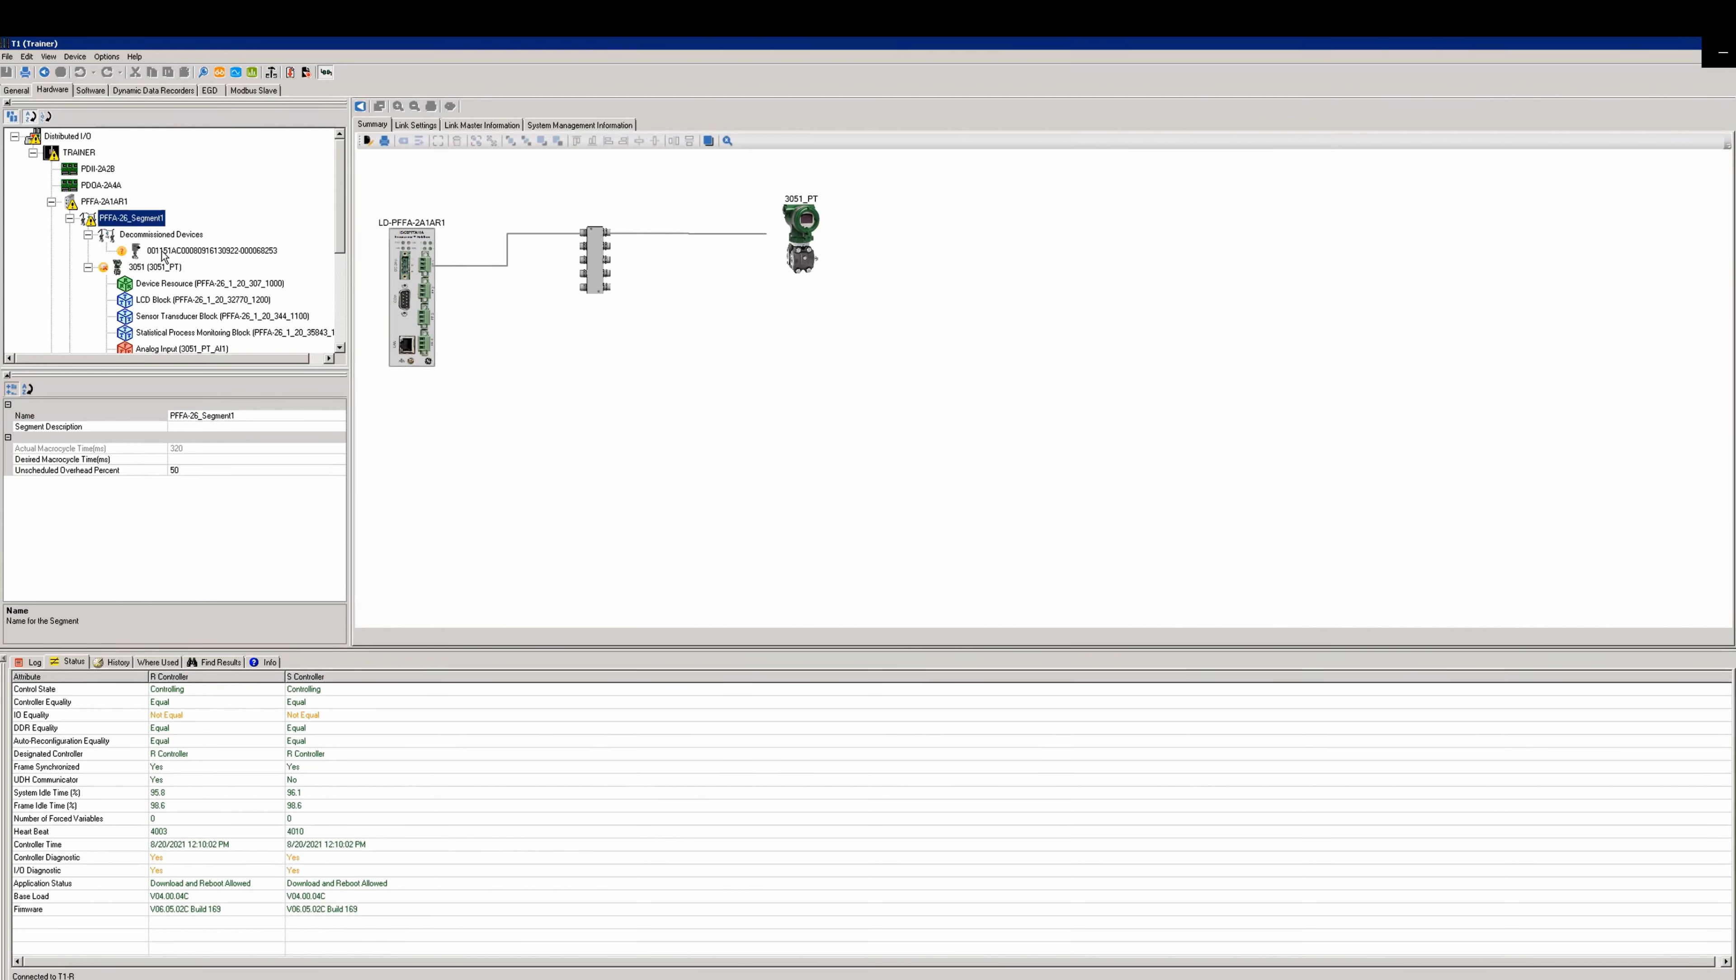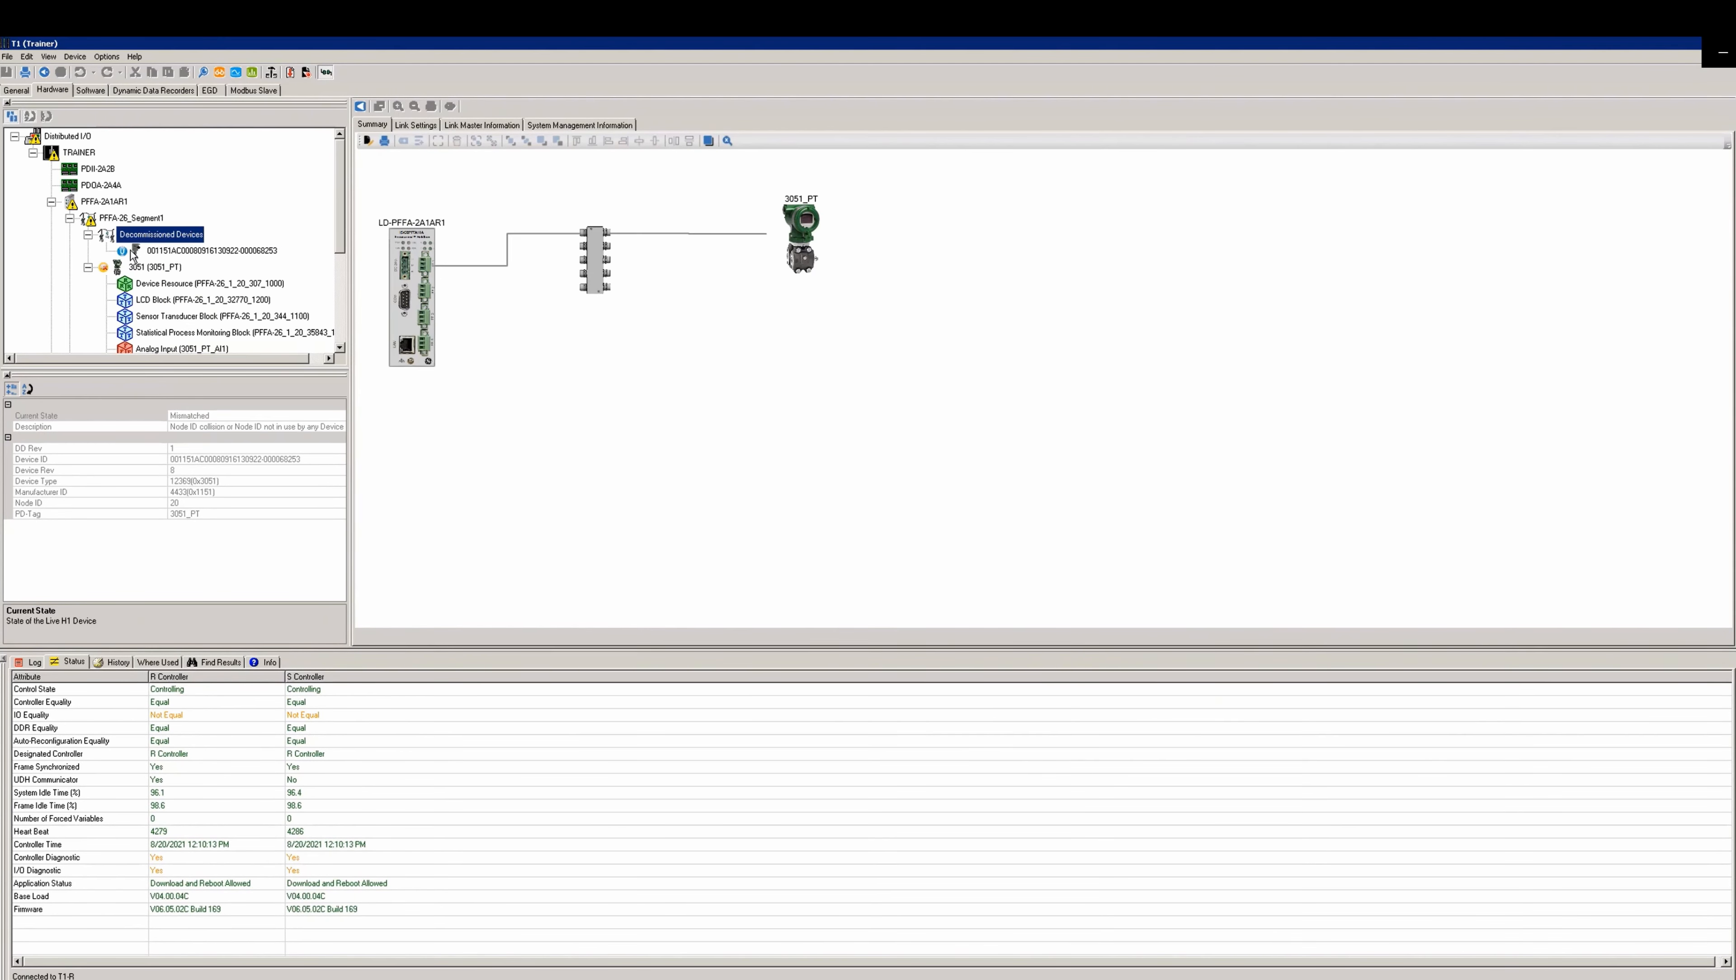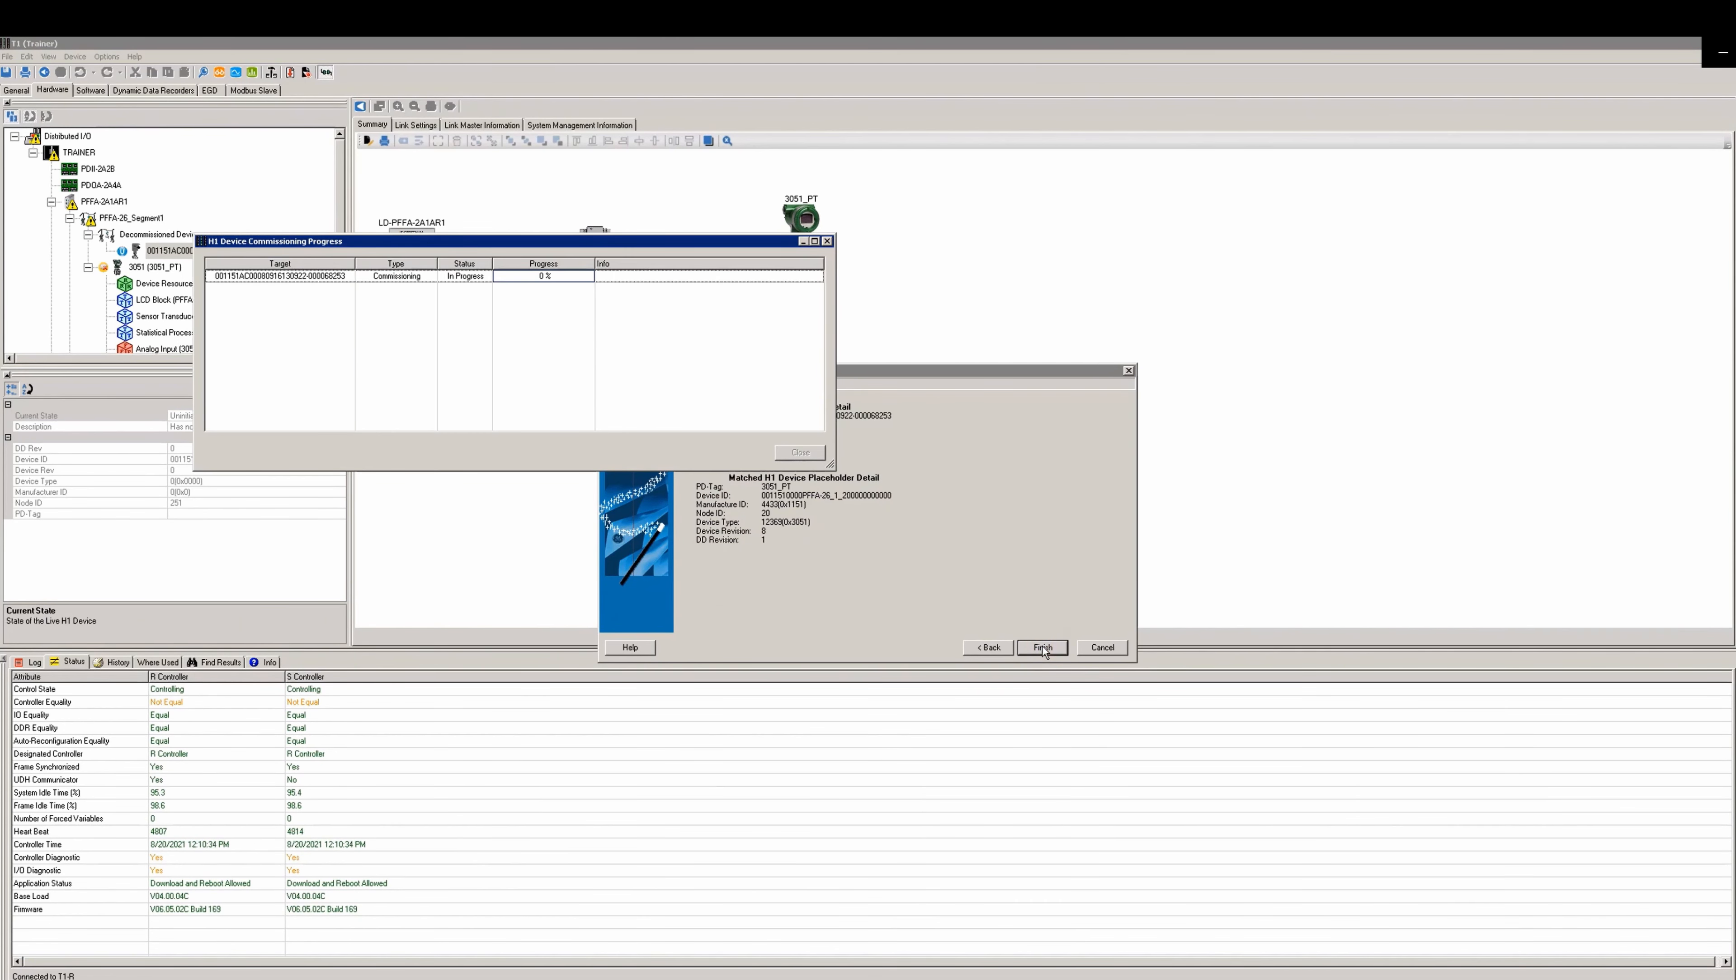Go to the segment where you added the new device and expand the decommissioned devices. Right-click the new device and select clear. After it clears, close the window that popped up. Right-click on the device and select commission. You'll get a wizard that opens and you'll select the container that matches the device. Now select finish and the device will begin to commission.